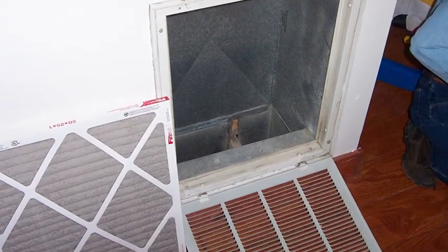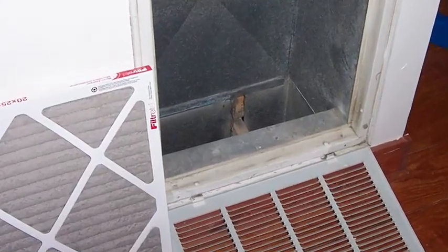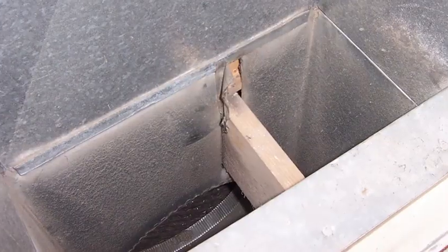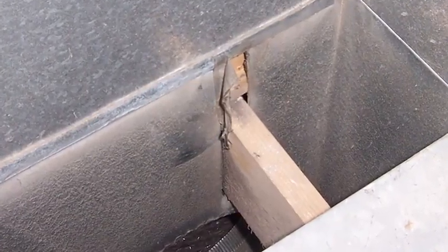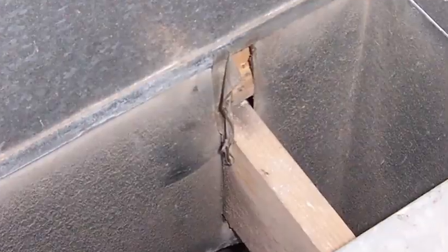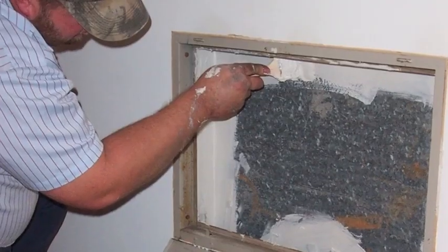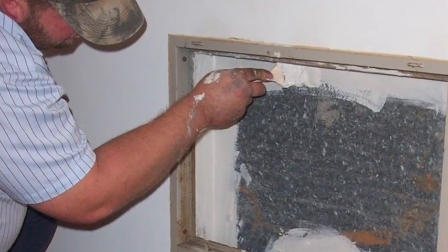The minimum is when we see just a small amount of wood and sheetrock in some returns, usually right behind the return grill, where perhaps a return can and ductwork then take over. Usually easy to seal. If the leaks are too big for AeroSeal, reaching through the opening for a bit of hand sealing will usually do the trick.